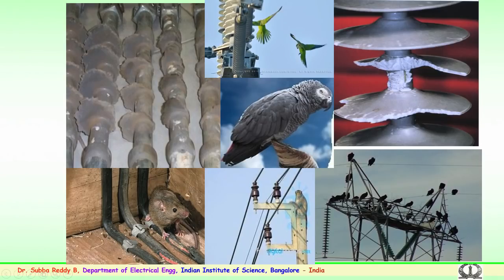Similarly, bird droppings are again a very serious issue. Bird droppings on the insulator surface over a period of time form a conductive fluid on the surface where the insulator starts conducting, and failures have been noticed because of bird droppings over a period of time, or because bird droppings in combination with fog or mist could make the surface conductive and degrade the surface. So, several of these issues are also of serious concern to the utilities in the proper functioning of the transmission network.